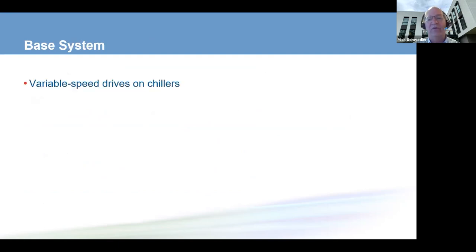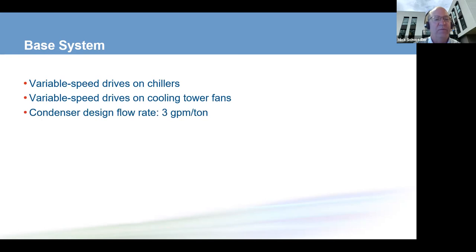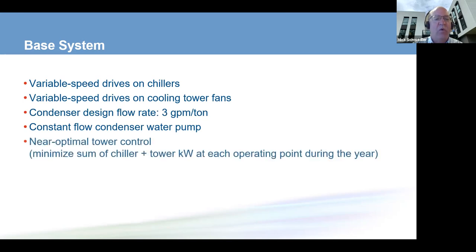We're going to go through a couple system types. We're going to start with variable speed drives on all the chillers. Not necessarily optimal, but that's what we're going to start with. Then variable speed drives on the cooling tower fans. That's required in most cases by ASHRAE Standard 90.1 and your local energy code. We're going to start with the condenser design flow rate of 3 GPM per ton, which with less efficient chillers was a 10 degree delta T. With today's chillers, it's 9.3 to 9.4 degrees. And a constant flow condenser water pump. We're going to control the leaving tower set point so that the sum of chiller plus tower energy consumption is at its lowest. And we're going to balance those two to get the optimal system control.